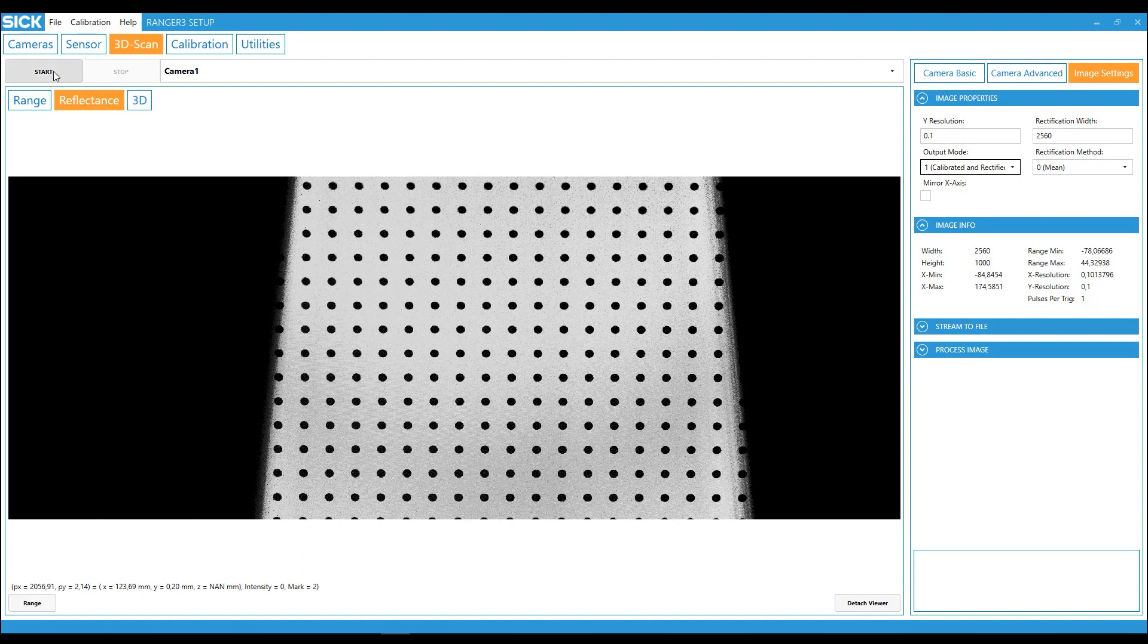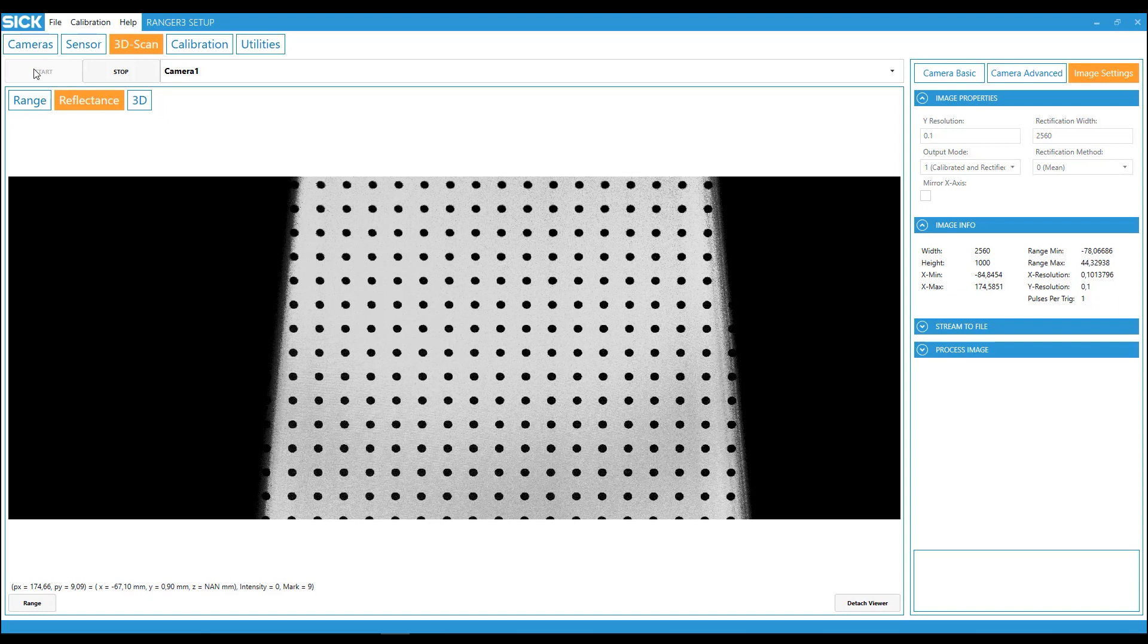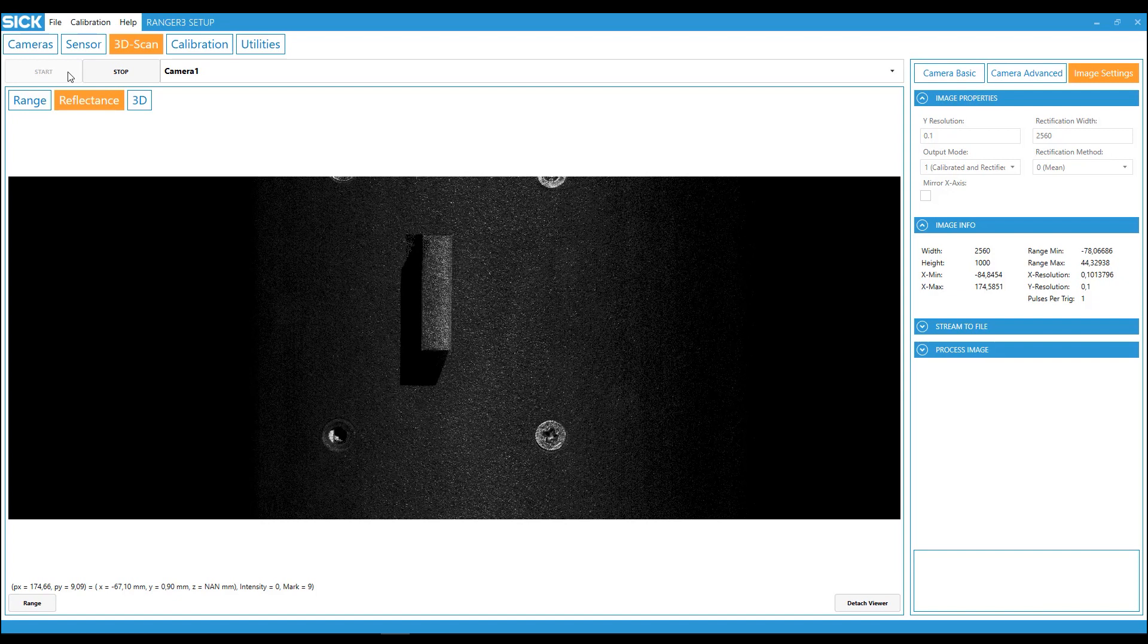Make a scan. And the last step is verification. Scan an object with known height and width, for example a gauge block. After that, measure the object. And if needed, adjust the calibration parameters and redo the calibration.